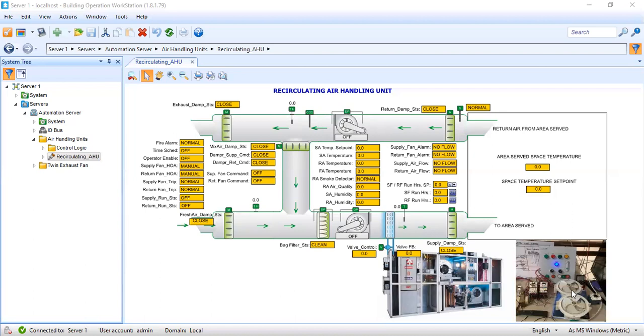I have here two small fans — this one is for my supply fan and this one for my return fan. I have some pilot lamps in my control panel, then the selector switch. The selector switch will tell our air handling unit if it is in auto, manual, or off position. The important thing in a motor control is the selector switch, because the BMS will take control if the equipment is in automatic. My first task today is to show you how I am going to bind these six objects into my IO modules.